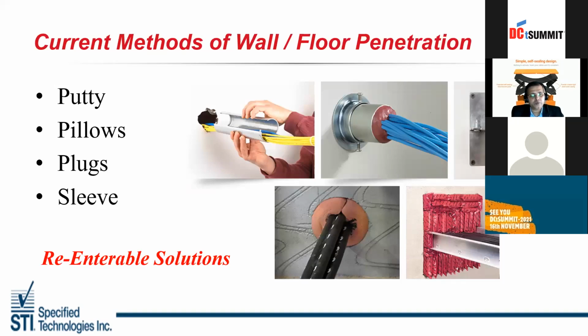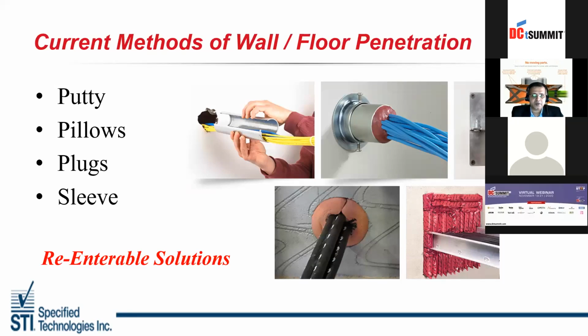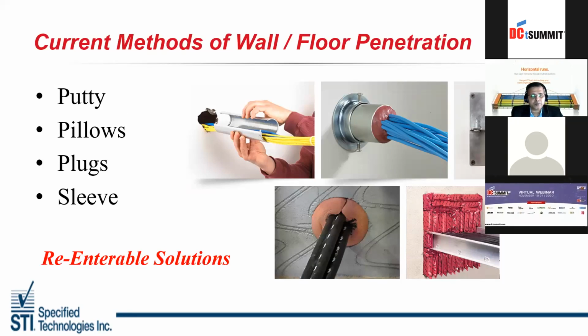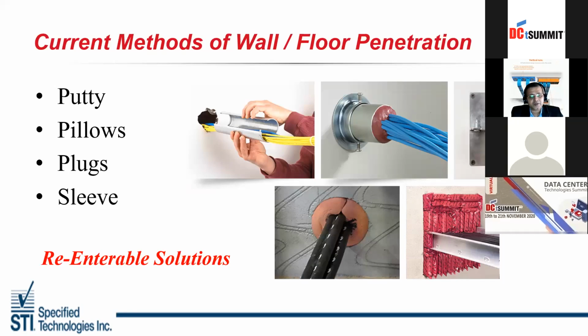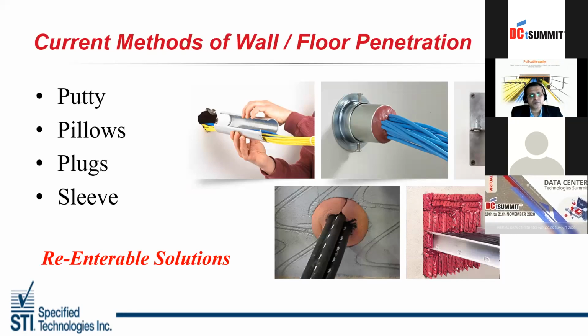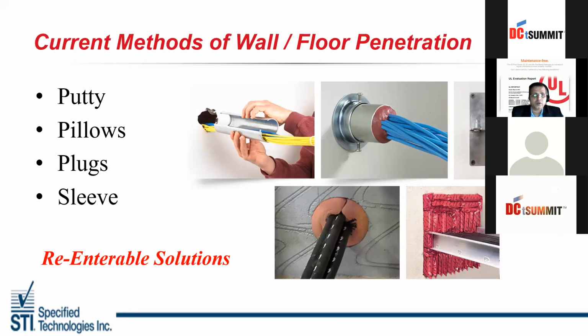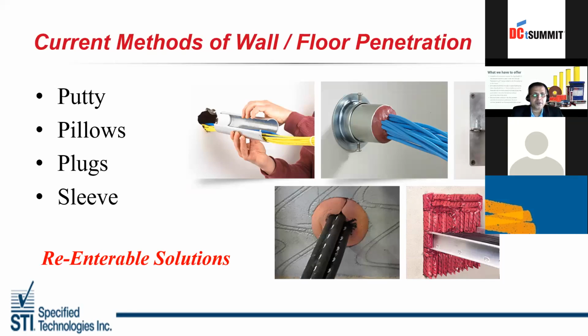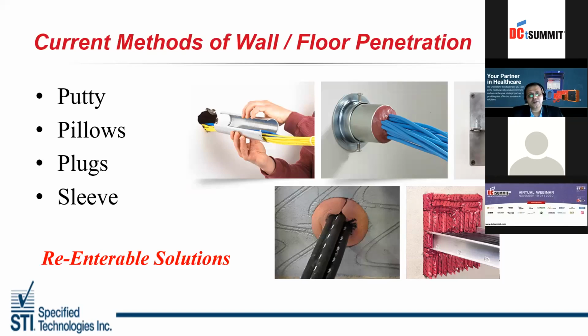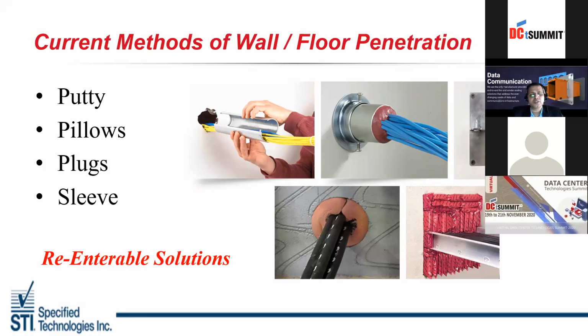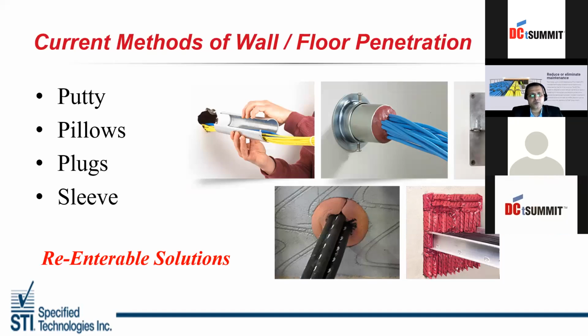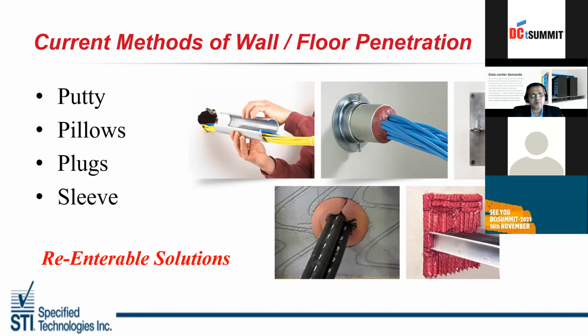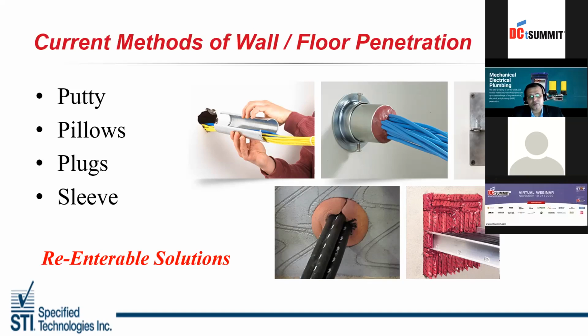Current methods for wall and floor penetrations: there are two ways of stopping or redoing a product. One is re-enterable and one is a permanent solution. So it depends upon the owners of the building whether they want to go for a re-enterable solution or a permanent solution. Re-enterable solutions are where you foresee that the cables or the pipes or the cable trays have to be changed or added in the coming 6 months or one year down the line. So what you're investing right now will remain as it is. Like you have putties, you have pillows, you have plugs, you have sleeves.